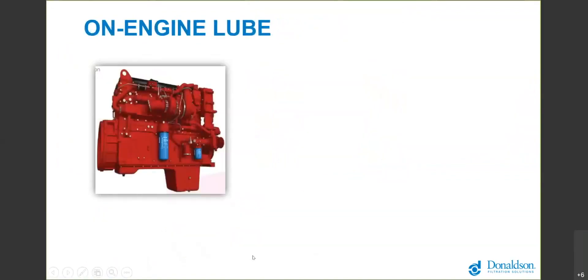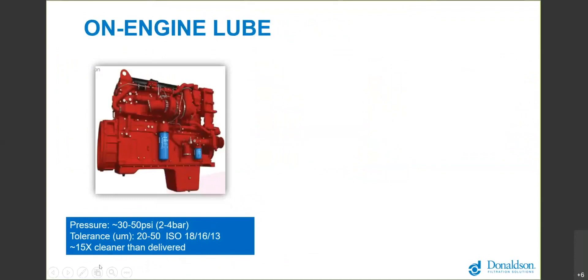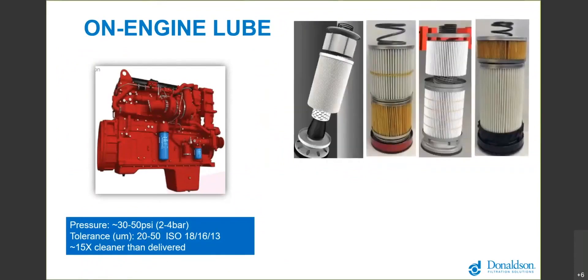Transitioning from fuel to lube, this is an on-engine lube filter, typically between 30 and 50 psi working pressure. That means the particles that we really care about are between 20 and 50 microns in size. That's why we target an ISO code of 18/16/13, and typically that's about a 15 times cleanliness improvement than what's being delivered currently to your equipment.